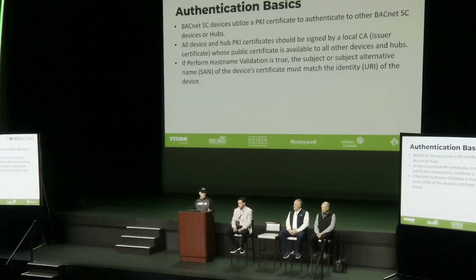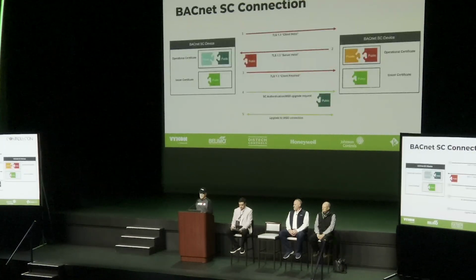The intention of this is that there would be a local certificate authority that gets set up by the end customer or you as the contractor that's installing, and you're going to use that local CA certificate to digitally sign all the server certificates for all of the BACnet SC devices on the network.